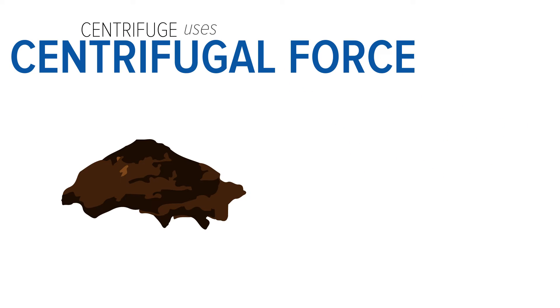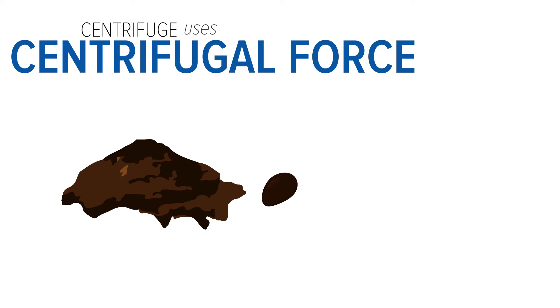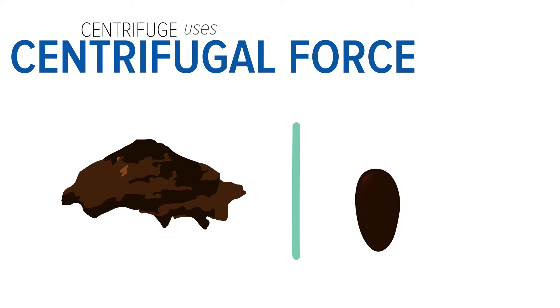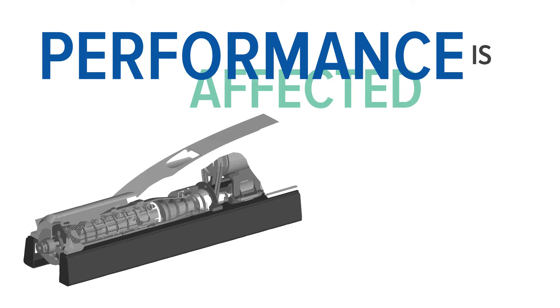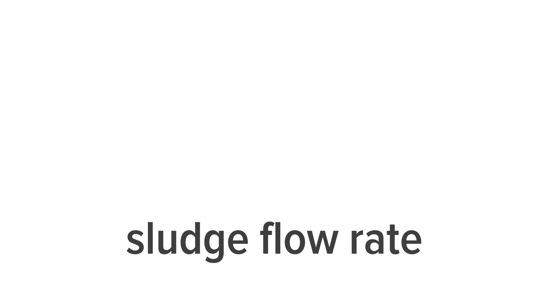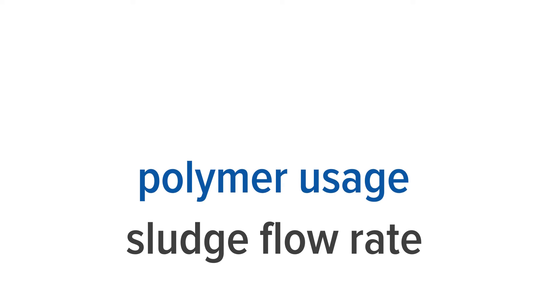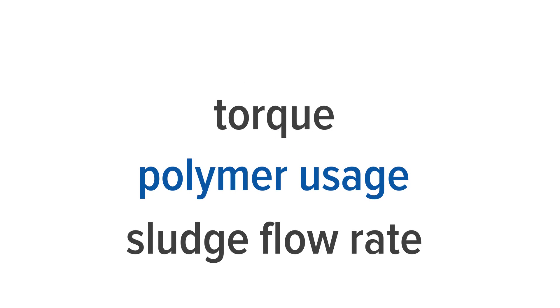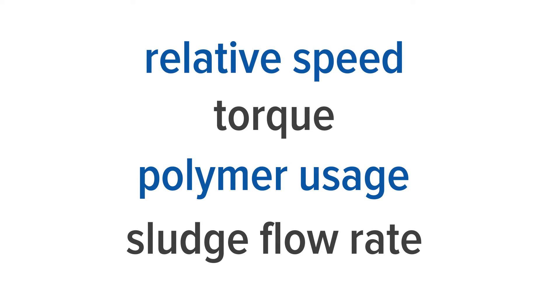The centrifuge uses centrifugal force to separate the solid from the liquid, and the performance is affected by the sludge feed rate, polymer dosing rate, the torque, and the relative speed between the bowl and the scroll.